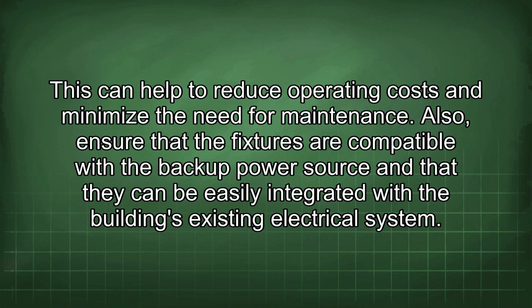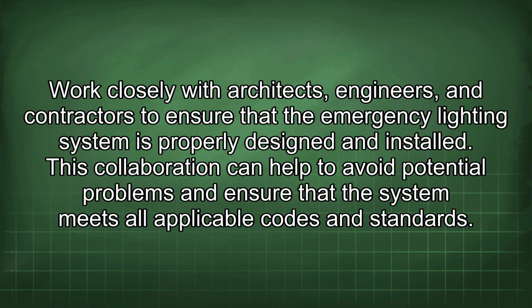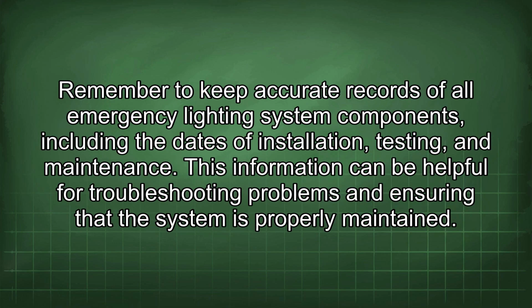Also, ensure that the fixtures are compatible with a backup power source and that they can be easily integrated with the building's existing electrical system. Work closely with architects, engineers, and contractors to ensure that the emergency lighting system is properly designed and installed. This collaboration can help to avoid potential problems and ensure that the system meets all applicable codes and standards. Remember to keep accurate records of all emergency lighting system components, including the dates of installation, testing, and maintenance. This information can be helpful for troubleshooting problems and ensuring that the system is properly maintained.